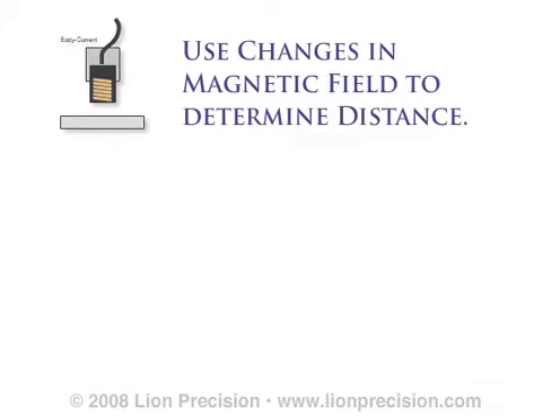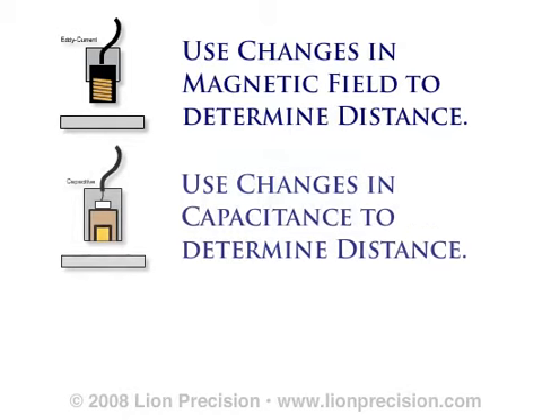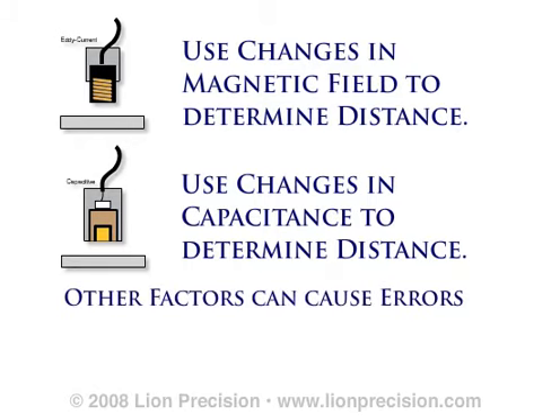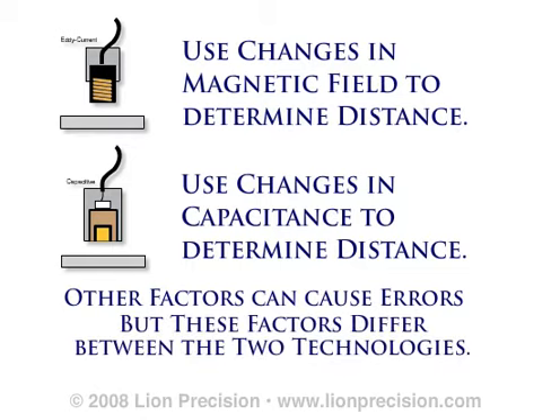Eddy current sensors use changes in magnetic field to determine the distance to the target. Capacitive sensors use changes in capacitance. There are factors other than the distance to the target that can also change a magnetic field or the capacitance. These factors represent potential error sources in your application. Fortunately, in most cases, these error sources are different for the two technologies. Understanding the presence and magnitude of these error sources in your application will help you choose the best sensing technology. The remainder of this presentation will explain these error sources so that you can make the best choice for your application and get the best possible results.